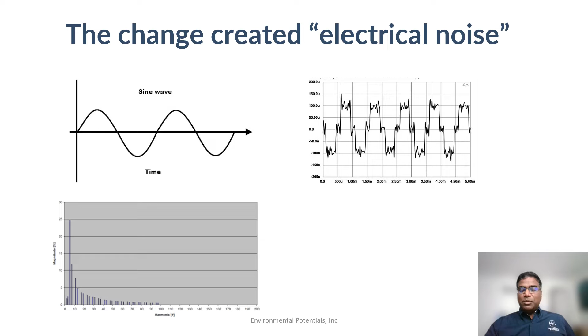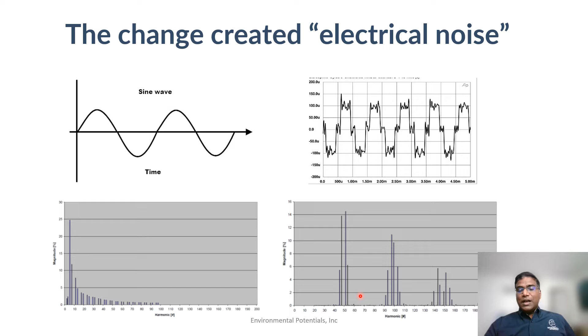Here it used to be a high third harmonic from traditional induction motor loads. Now with the addition of nonlinear loads in the facility that are switching at a higher frequency, you can see that the noise has been substantially increased on the higher frequency spectrum. Again, the perfect sinusoidal wave is no more sinusoidal, and in the frequency spectrum, the high third harmonic is no longer a high third harmonic, but they are all over the spectrum. This is because of using the SMPS, switch mode power supplies, in a facility.